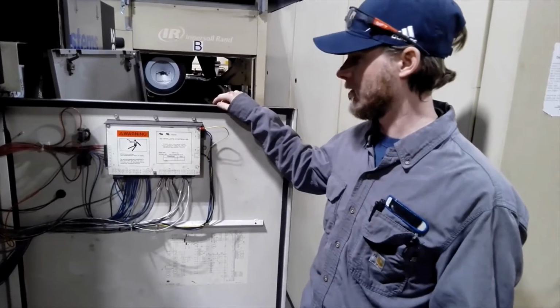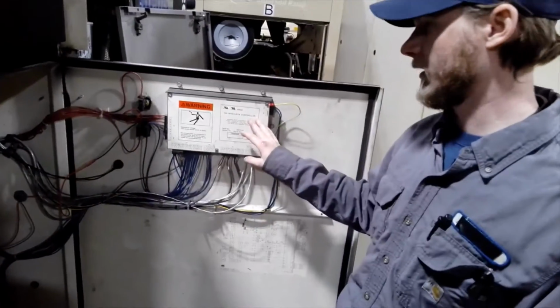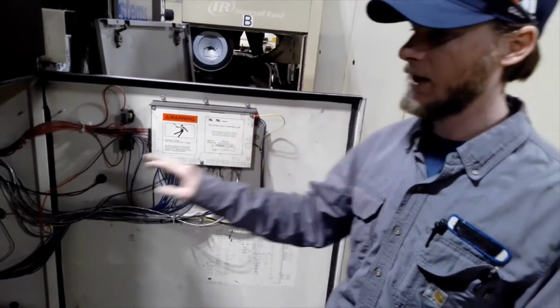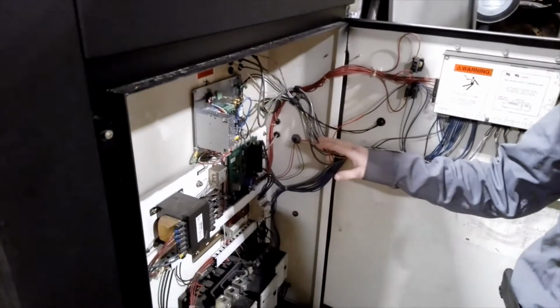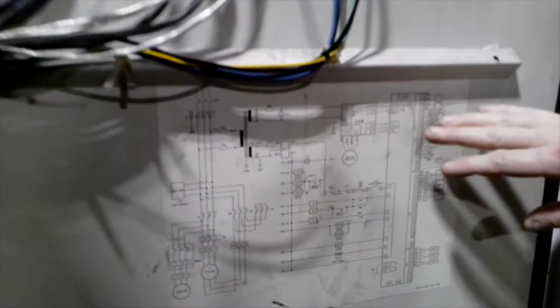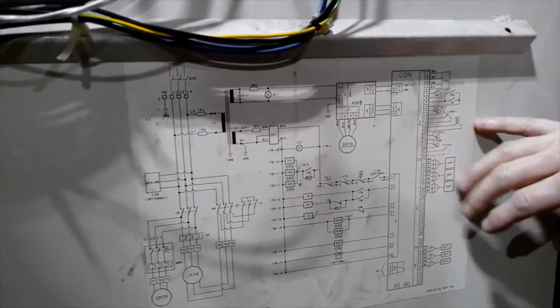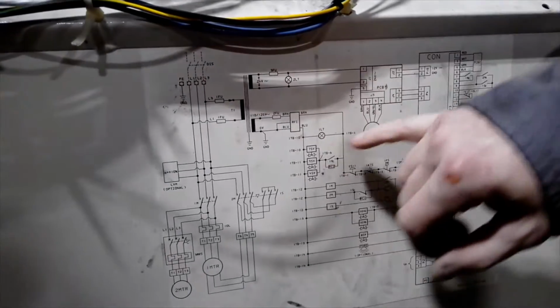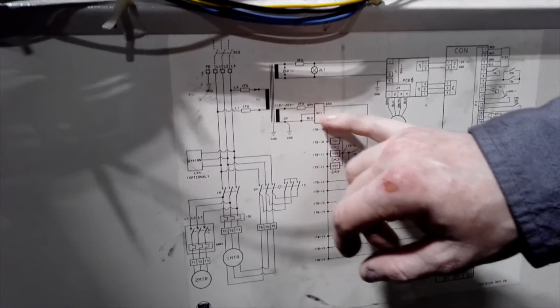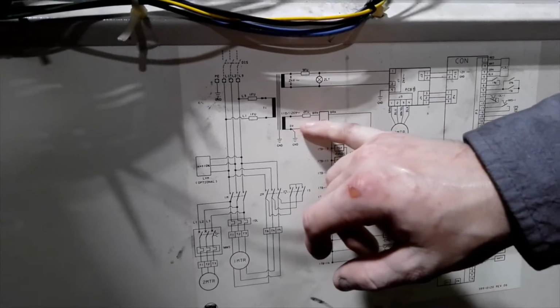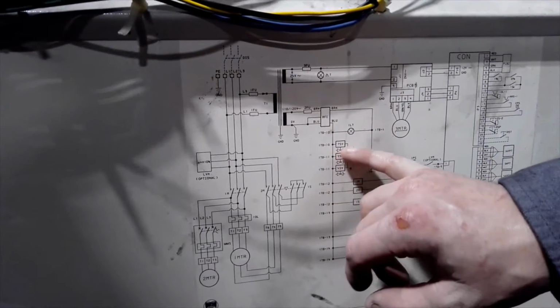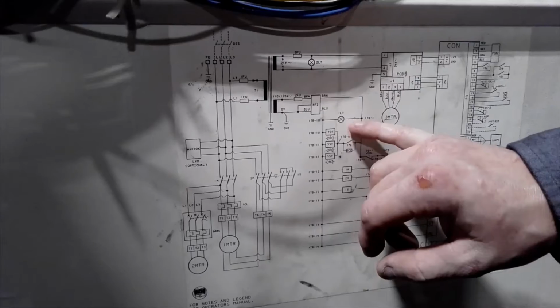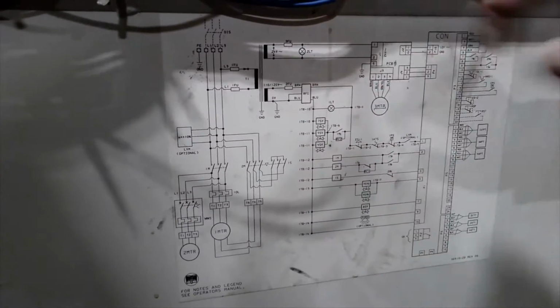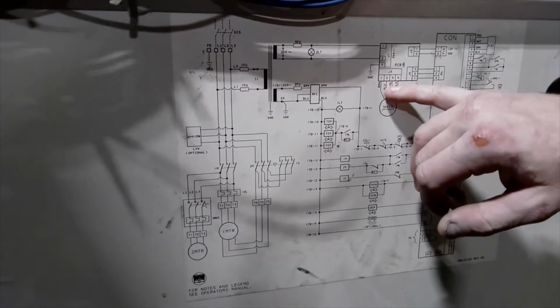Alright, we're back. We've got our power connected, we have our controller connected. Now for the power, you're going to need 110 volts. For that, you'll have to find a wiring schematic. Luckily, ours is right here on the door, so we'll trace that down from the transformer to our 110. You'll want to be after your fuse but before your e-stop, so that if for any reason somebody hits that e-stop, you're not going to lose communication.